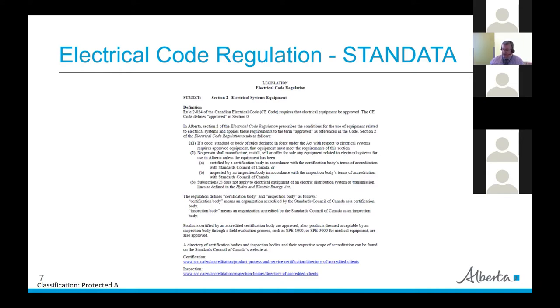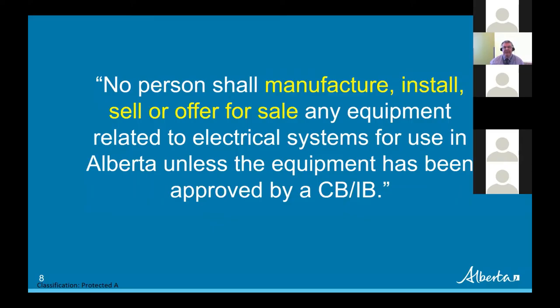Hopefully we see something on that soon. As soon as I see it, I'll be letting the Safety Codes Council know. To repeat: no person shall manufacture, install, sell, or offer for sale any electrical equipment in Alberta unless it's been approved by a CB or an IB — that's a certification body or an inspection body — again, in the context of equipment, not installations.